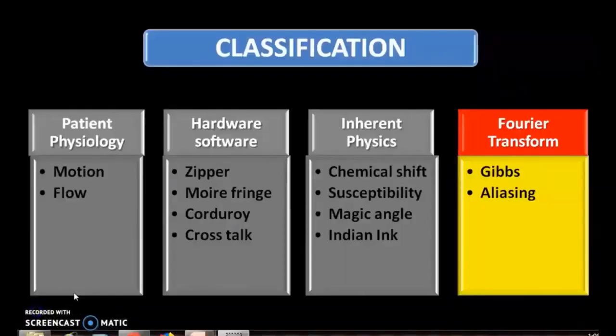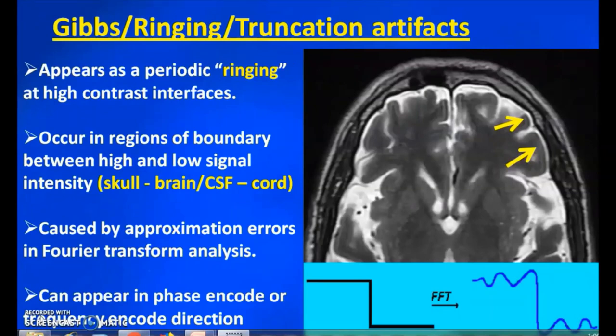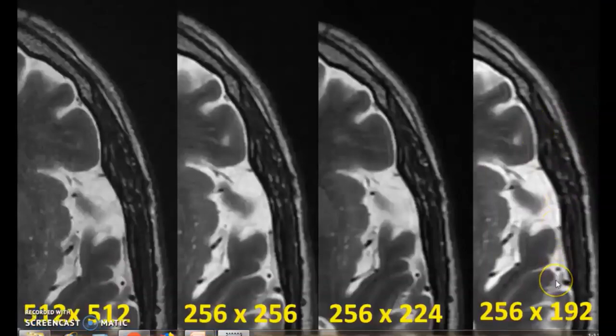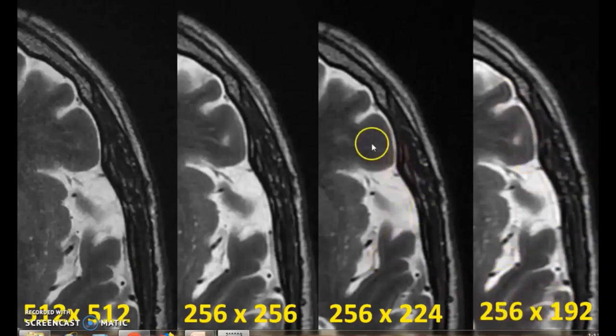The final classification is Fourier transformation-related artifacts — the Gibbs ringing artifact. It appears as periodic ringing at high-contrast interfaces occurring at boundaries between high and low signal intensities, such as skull-brain or CSF-cord interfaces, seen as multiple lines along the planes of the boundaries. By increasing the matrix, this kind of Gibbs artifact can be eliminated. You can see multiple white lines with a low matrix, which are gradually reduced by increasing the matrix, and with a high matrix it is completely eliminated.